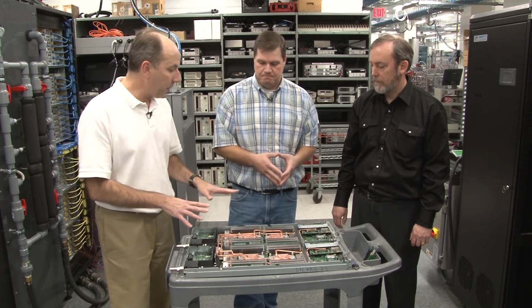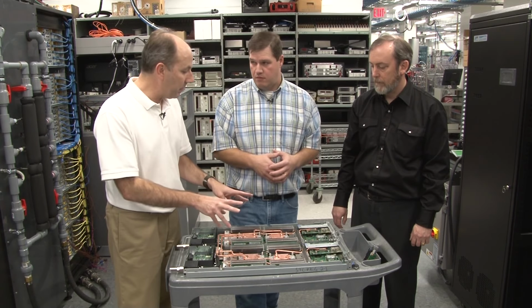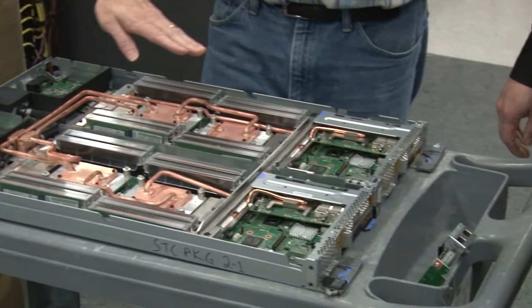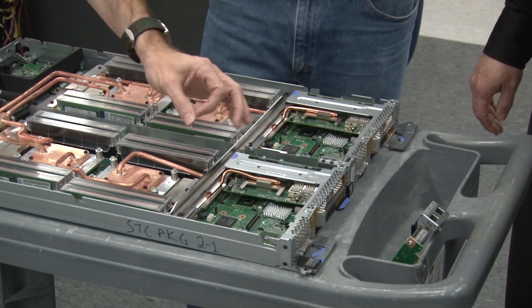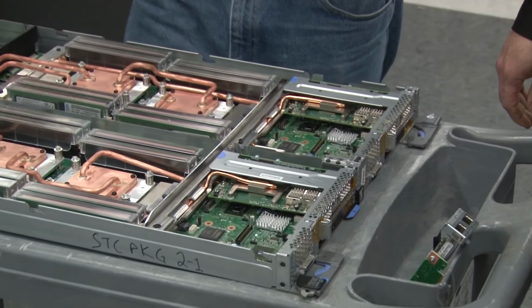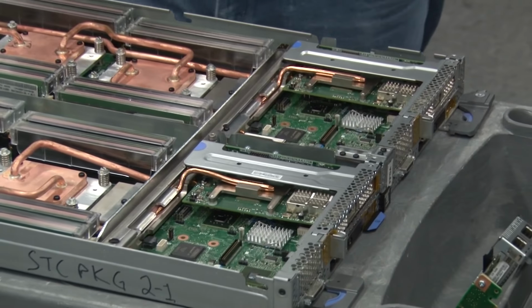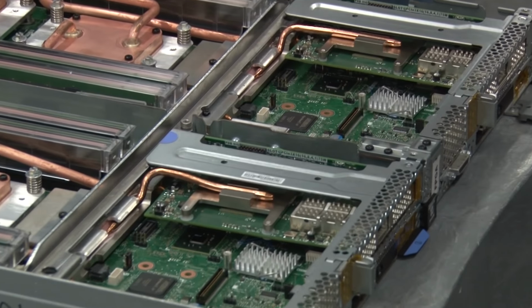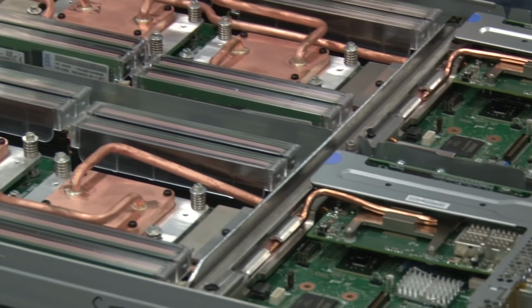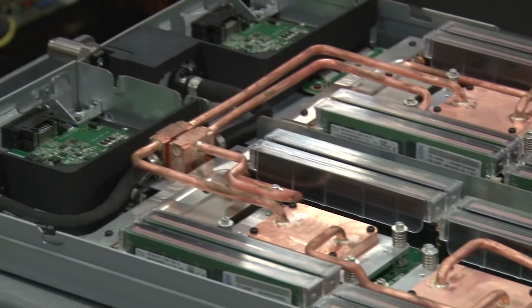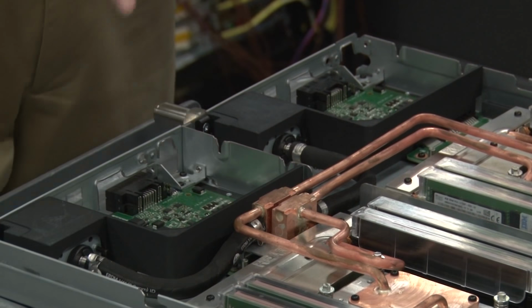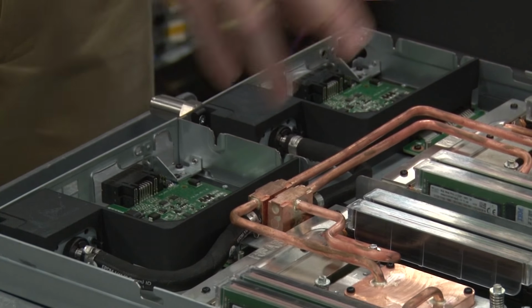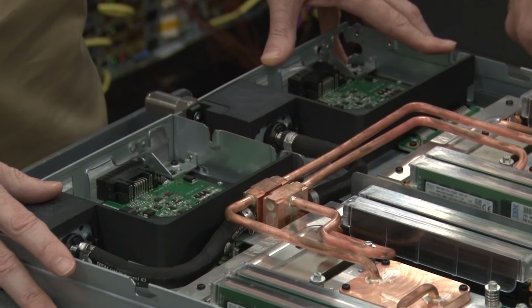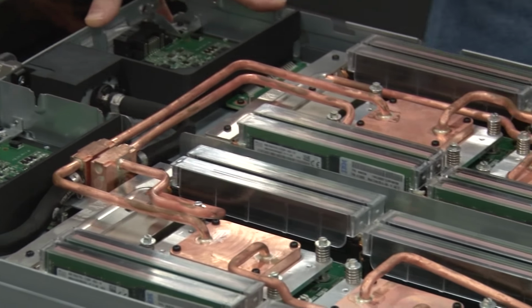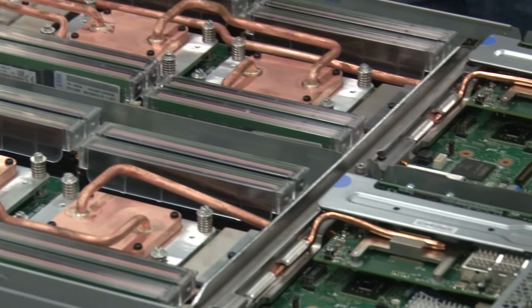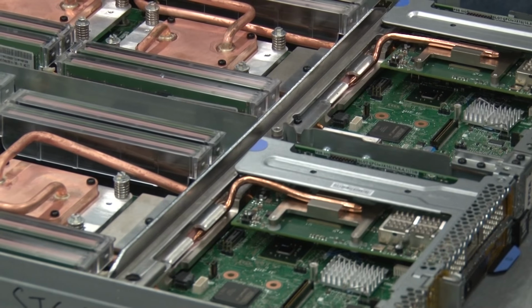So the copper piping cools the processors, memory, and the adapters up front. The rest of the components, the small chips in front, are cooled by the power supply fans, making use of a little bit of airflow from the power supplies. That's what's been tested all this time, evaluating all the temperature settings, making sure everything remains sufficiently cool, and that we're meeting the thermal specs of all the components in the system.